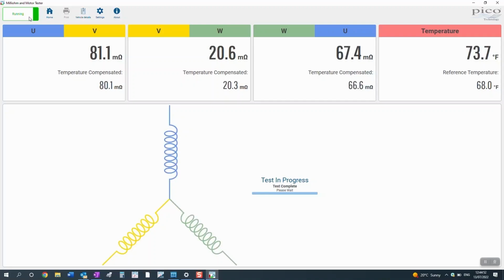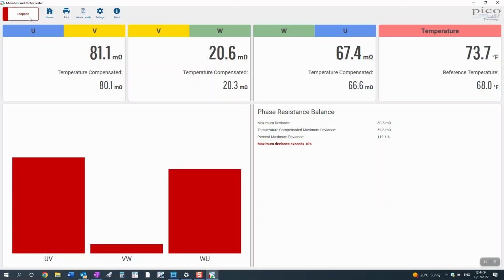Yeah. Notice temperature compensated there. Of course, that has changed. We've got such a huge deviation between phases. That is a fail. So it's a test over and above the isolation test.